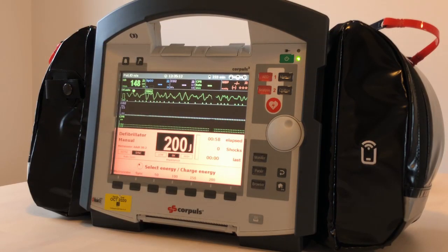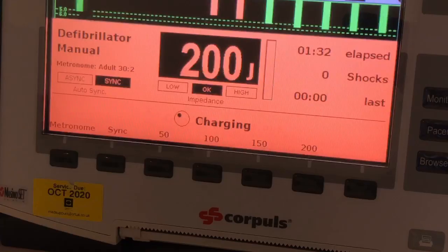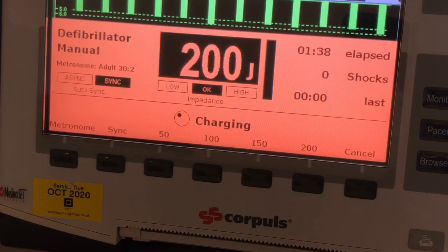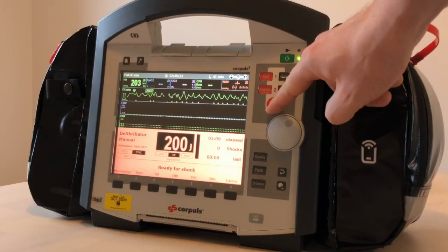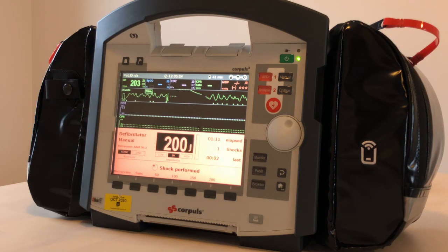In manual mode, charge the device by pushing the charge button. When the shock ready tone sounds, push and hold the shock button to deliver the shock. If you do not wish to deliver the shock, press the cancel button.